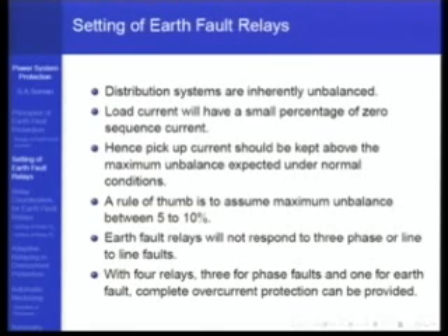I mean, if you put it below 10 amperes, then it will start operating on system unbalance, which you don't want it to operate on. So there is a lower limit on the pickup current, which is 5 to 10 amperes. If 100 amperes is the load current, the phase relay picks up at 125 amperes. So you cannot detect a phase fault below 125, but an earth fault you can detect anywhere above 10 amperes. That's why you need a separate earth fault relay, because it gives you high sensitivity in the protection. Without that, your sensitivity is not there. And most of the faults that we face in real life have a high percentage of earth fault.